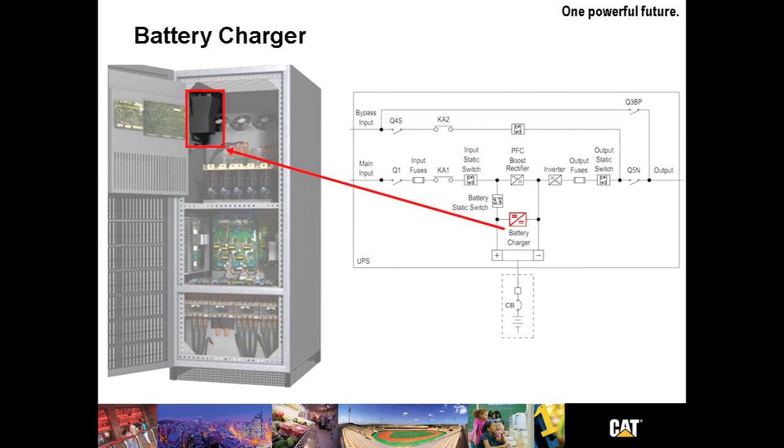Here you see the battery charger. The battery charger draws power from the 800 volt DC bus. Depending on the rating of the UPS, the charger will deliver between 18 and 50 amps for the purposes of battery charging. The charging system is sized to recharge a battery offering 30 minutes of backup time in less than 8 hours.